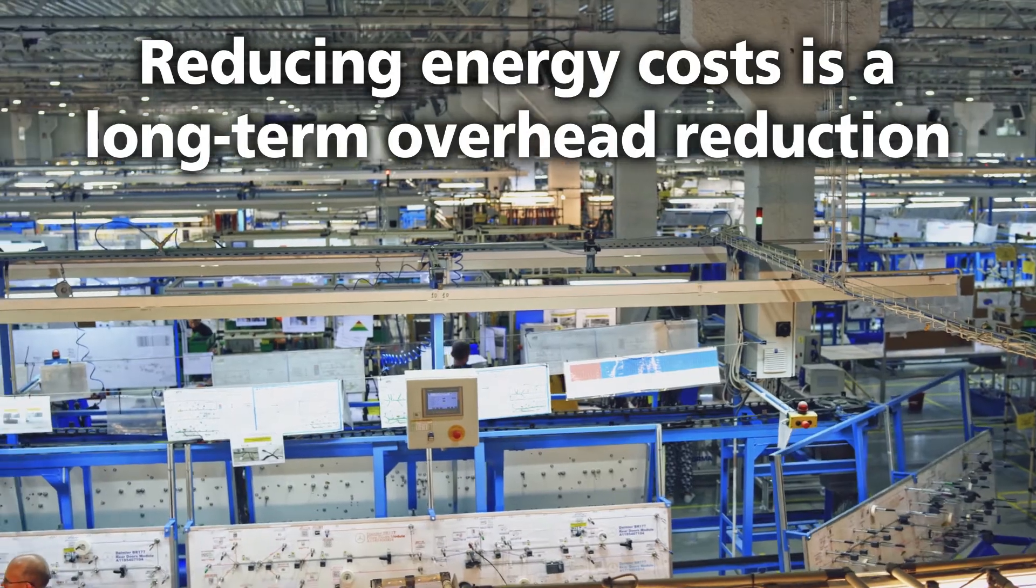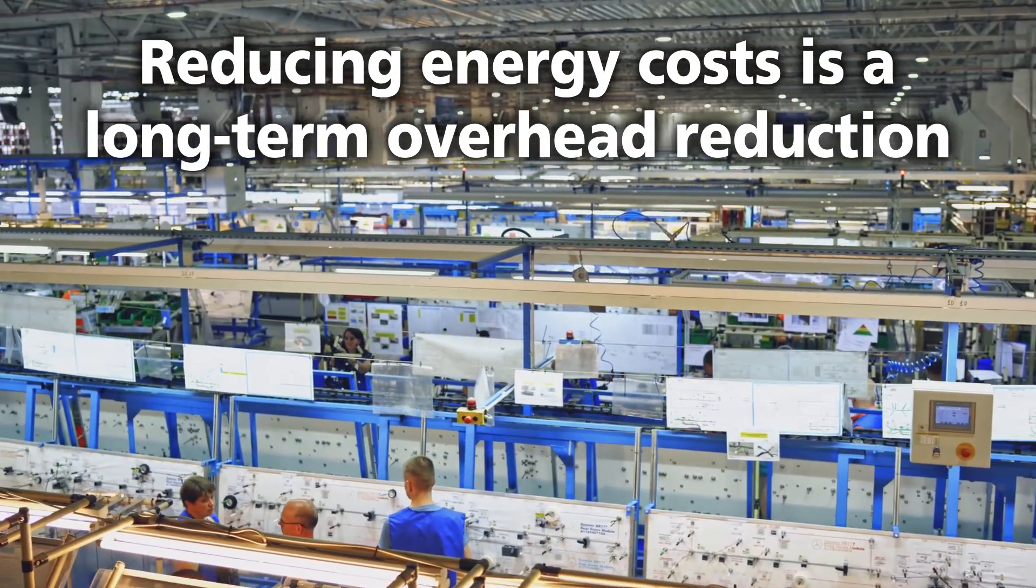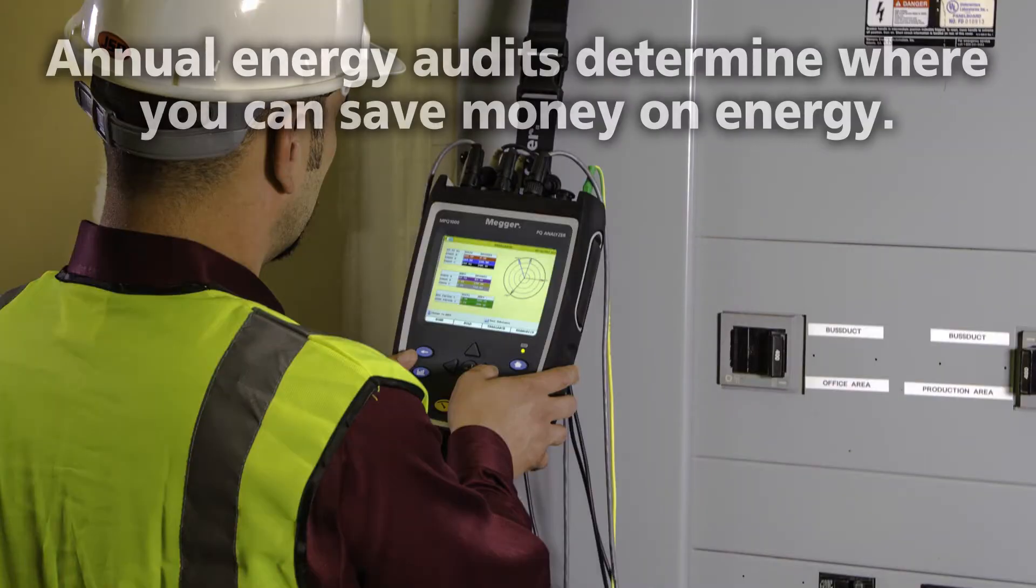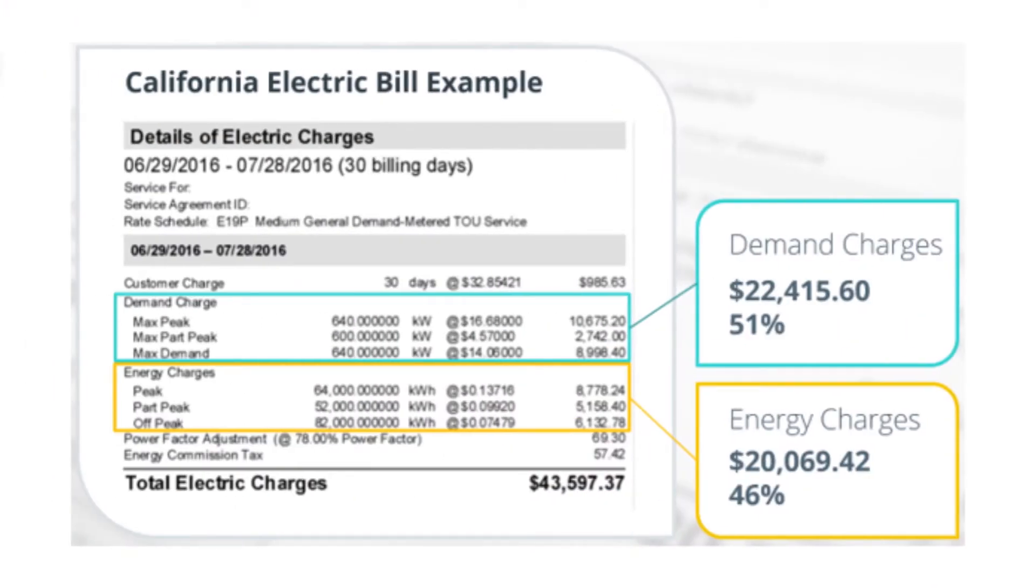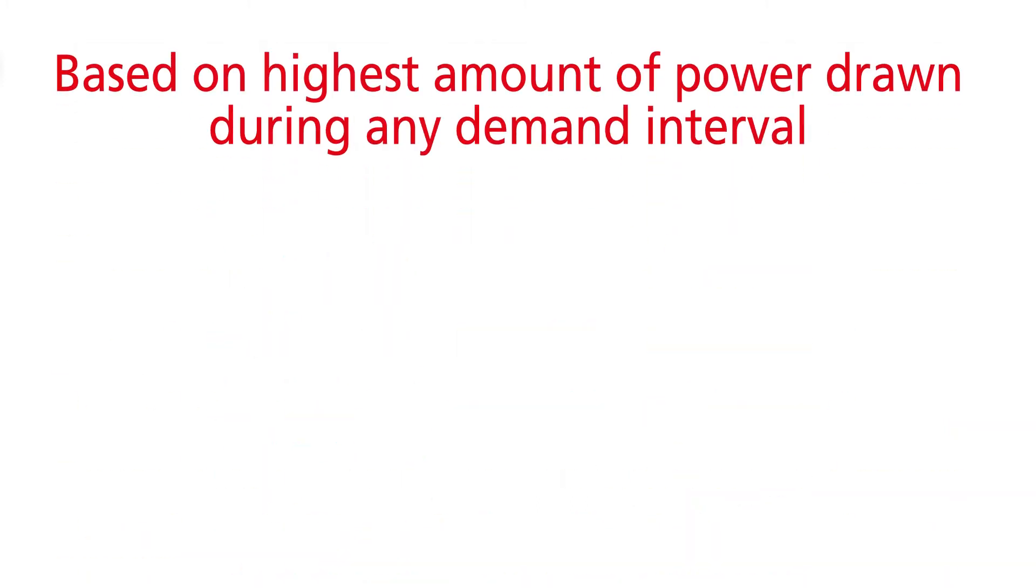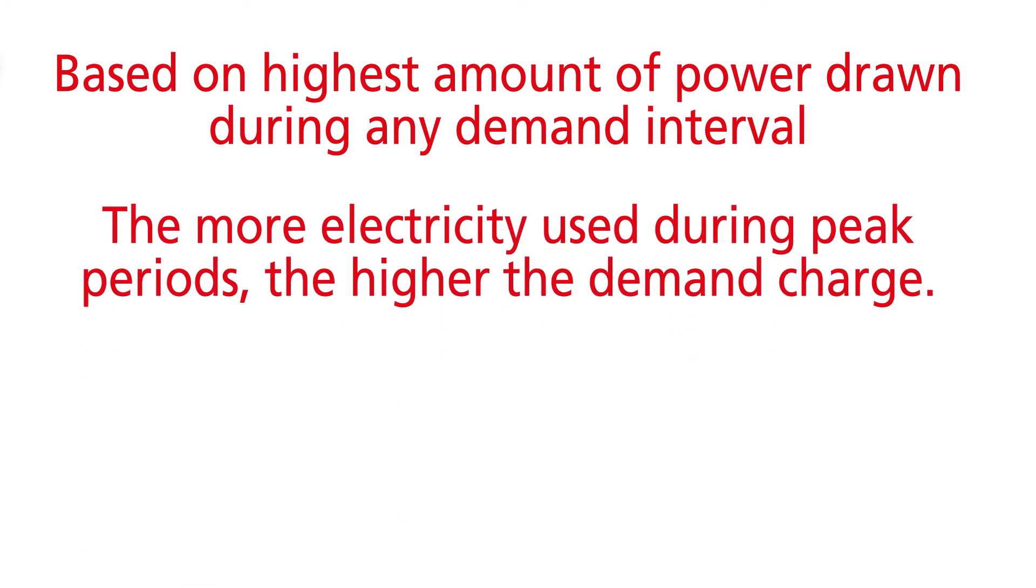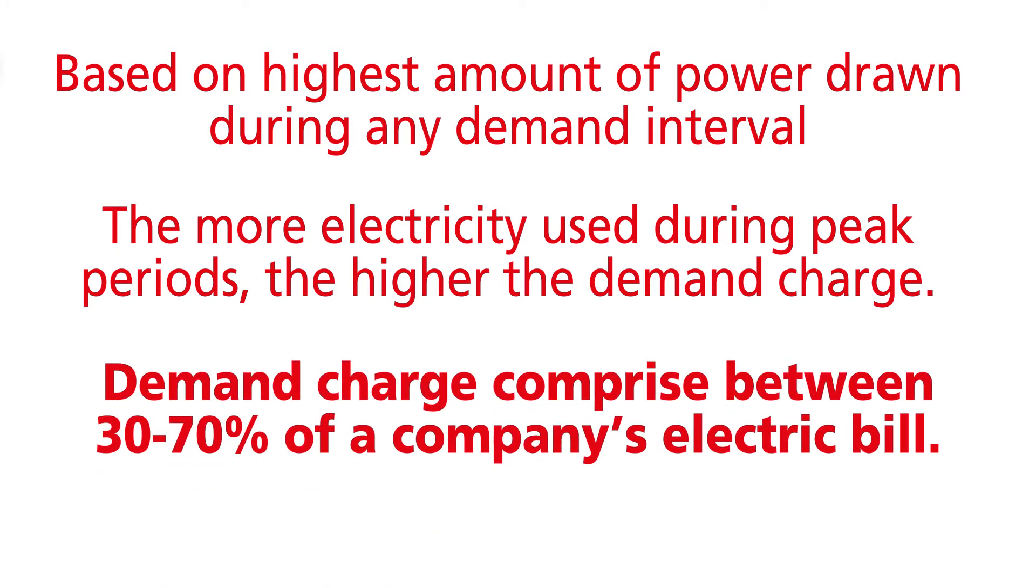Reducing energy costs is a long-term overhead reduction that can be beneficial to both management and labor. Performing annual energy audits is a way to determine where you can save the energy. Industrial energy is used based on demand rate. Distribution demand charge applies to both commercial and industrial entities that pay time of use rates or have certain bill sizes. It is based upon the highest amount of power drawn during any demand interval during the billing period. The more electricity you request during peak periods, the higher your demand charge can be. Demand charges can comprise between 30 and 70 percent of a company's electrical bill.